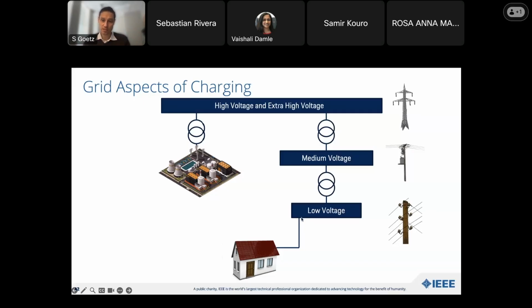And you had these nice bottlenecks at the transformer, where you could fuse the entire system. You could give every house a larger fuse, for example, whatever, 50 amps or so. The entire feeder might just allow 200, 400, 600 amps, so that might be just a fraction of n times the 50 amps that the houses have. But since you have the bottleneck here, you can give every house a little bit more, because you assume they will never use peak power at the same time.